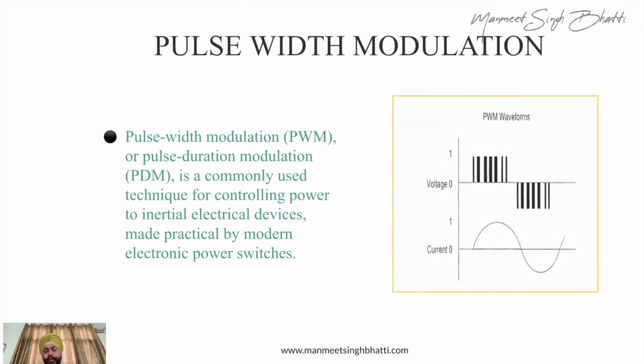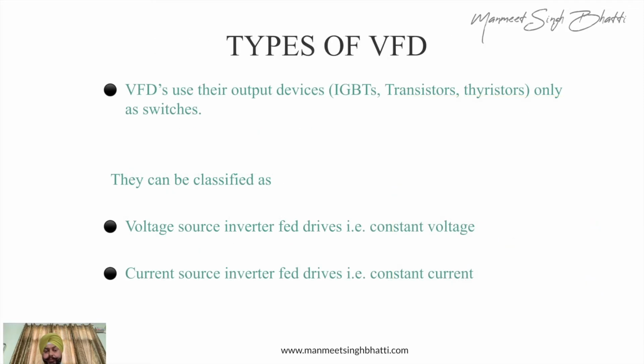So if you see the waveforms, you will see the change of the voltage coming up. In the width modulation, the voltage goes to one level, then it stops, it comes again, it stops, it comes again, and it comes down. This is basically the frequency which we are controlling from the switches, or you can say the inverter. And the current output based on this waveform is something similar to what is shown in the sinusoidal wave format. So basically this is what is going to change or control the motor.